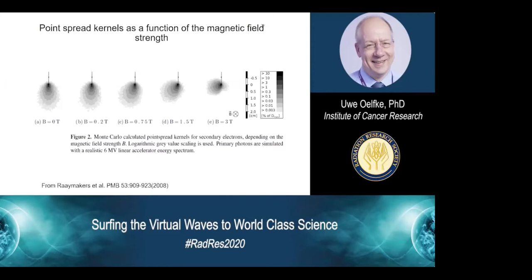You can see this even on a more basic level, usually used for dose calculations, a point spread kernel. You have a photon which is interacting, primary interactions set electrons in motion, and this is the dose kernel from the electrons which were transporting the energy away from the primary interaction point if there is no magnetic field. But if you now switch on the magnetic field perpendicular to the plane of the slide, then you see that the Lorentz force is deforming these electron kernels more and more, and this is exactly what also happens in the patient. So we have to account for these effects.